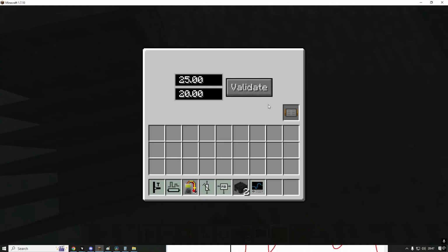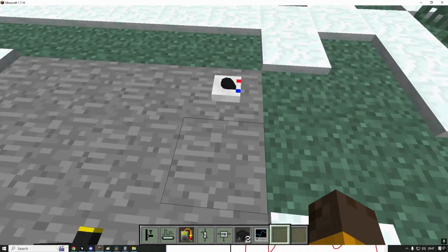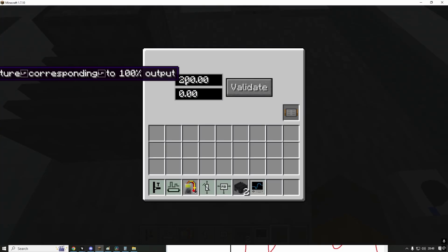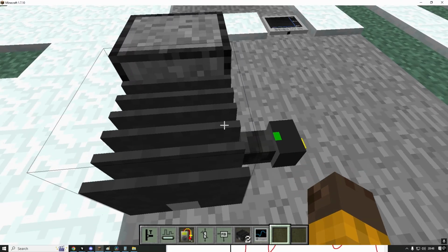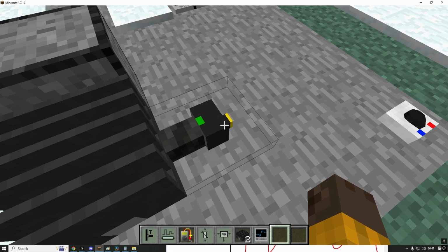Now in the probe we need to set the low value to 0. Extremely important to put 0 here. It will help you a lot. And the up value here we need to set a maximum value. So this instrument can select this temperature between 0 and 200. For example, you could set this to 300. My maximum temperature, I put this 200. It's fine for me.